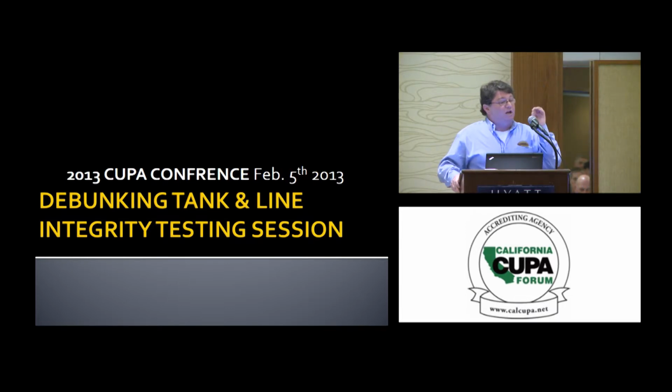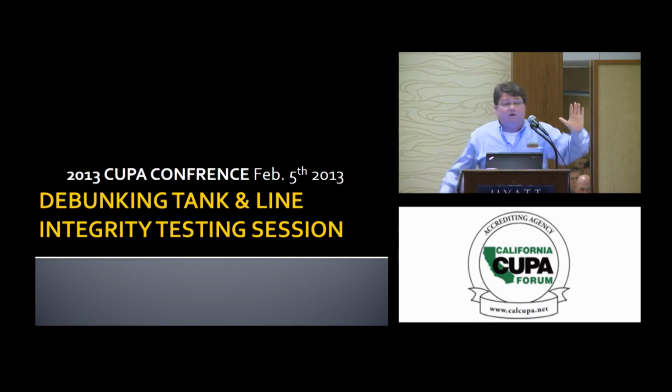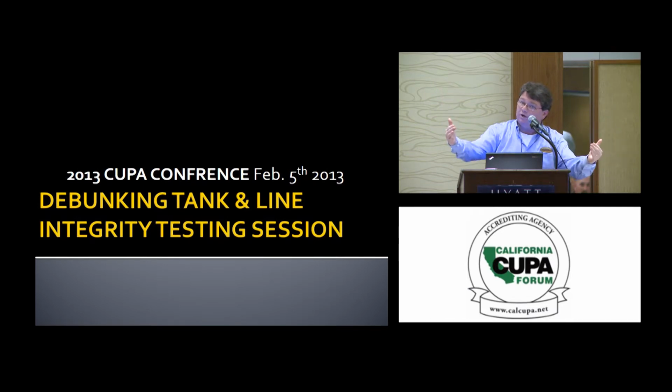So we came up with these tolerances. By the way, 0.1, that's a Coke can. That's a soda can, roughly, an hour, going into the ground on every tank and every pipe. Of course, that kind of drives me batty personally to think that we have a regulation of 0.1 on a piece of pipe that contains 5 gallons, and 0.1 on a 50,000-gallon tank. Somehow that doesn't jive with me. Less volume should be a tighter tolerance.